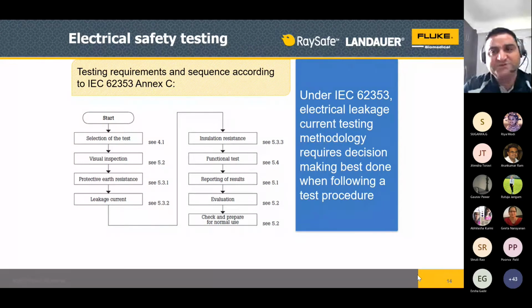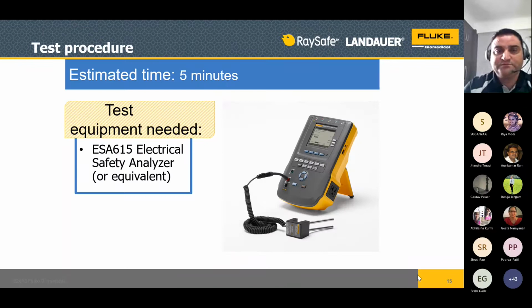Suppose we are talking about hospital environment testing, like under IEC 62353, you can start. See, this is a diagram which has been given as the testing requirements and sequence according to IEC 62353. You can start with selection of the test, visual inspection. As I said, you can see whether the leads are fine. Protective earth resistance you can check. Then you can check leakage currents, insulation resistance, functional tests, then reporting of results. Evaluation, you have to do evaluation also. Then check and prepare for normal use. Then again you can set it to the next test. The estimated time taken for electrical safety is 5 minutes if you do a test with the ESA 615.